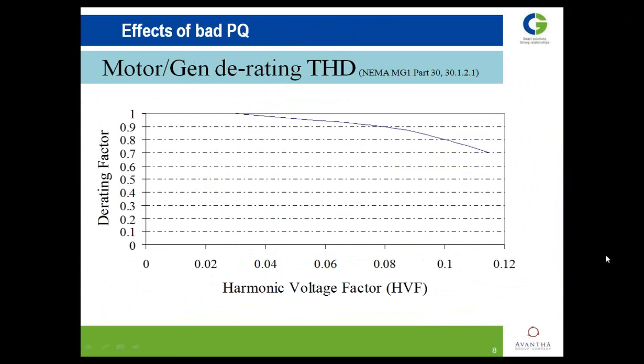I think this is one important one. Those who are hardcore about the real use of variable frequency drives know the impact of harmonics on the real load. If you look at NEMA MG1 part 30.1.2.1, the harmonic voltage factor and its impact. It means if my distribution utilities are giving me high THD supply, that has an indirect impact on my load. And I have experimentation showing that each 1% of added harmonics creates 0.35 to 0.37 added temperature rise in critical devices like a motor or generator. So that's one thing.